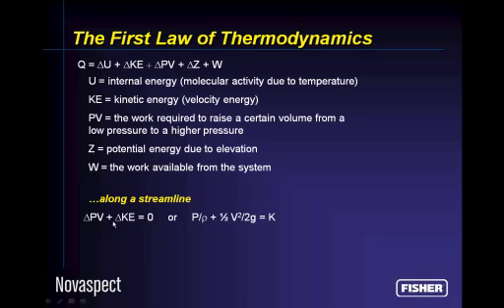But what's important is we can take the first law of thermodynamics and get rid of everything from it that's not applicable to fluid flow along a streamline, which is really what we're talking about today. It's a streamline of water or propane or ethylene glycol flowing through the control valve. And most of the terms in the first law of thermodynamics disappear except for the PV, the pressure volume energy, and the change in kinetic energy. These are the two terms that are left in our equation, and the law would be that the change in PV energy plus the change in the kinetic energy have to equal 0. One has to offset the other.